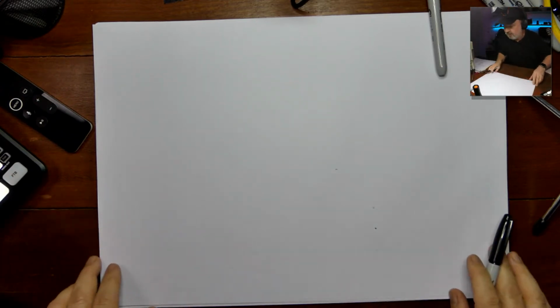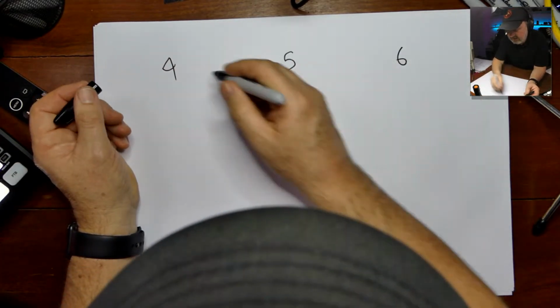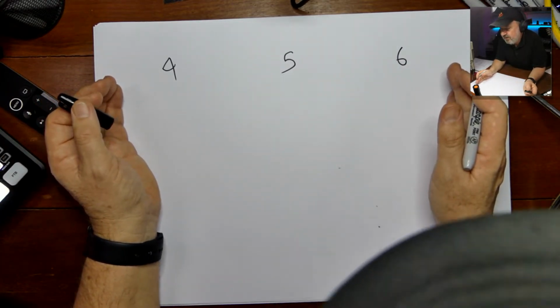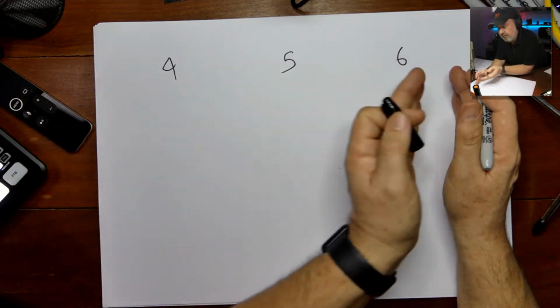sections within this standard. There are 3 categorizations of battery types, which we call sections: for a BESS, a battery system, and other. I'm just going to explain those real quick, so I'll jump over to my little drawing tablet. Okay, so 3 sections: 4, 5, and 6. The reason for those 3 sections is to make life easier for installers. If they know what type of battery system they're installing, they can straight away look at the relevant section and ignore the others.